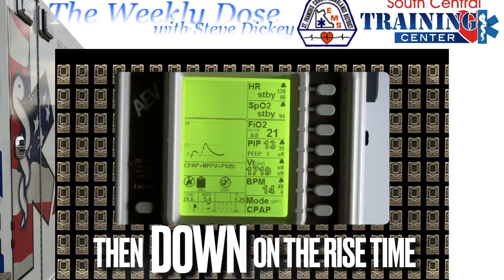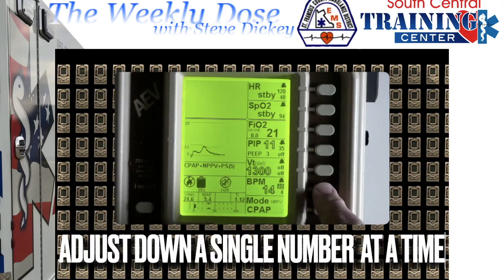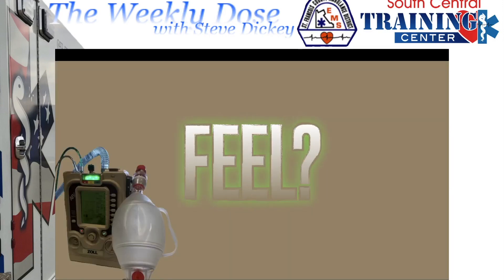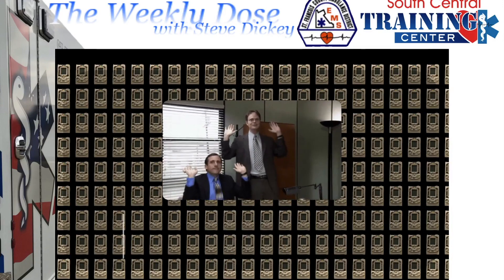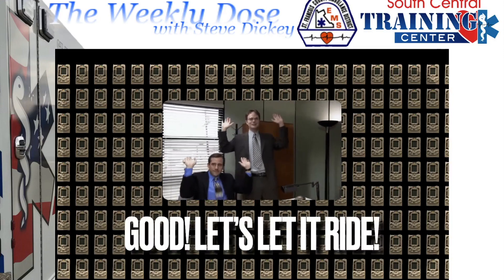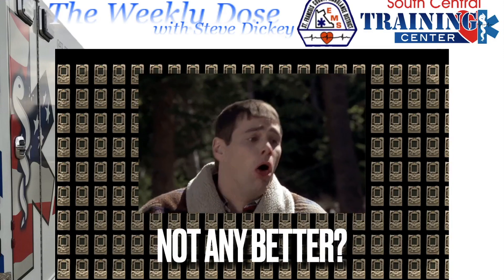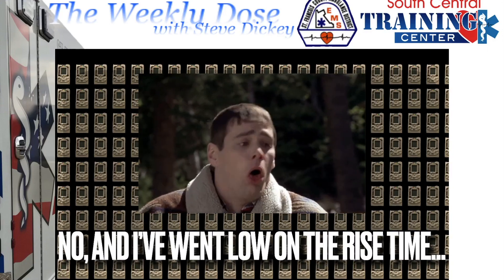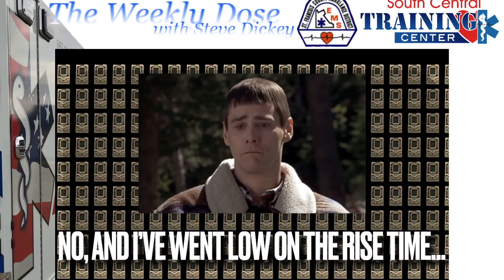When they're suffocating and cannot pull enough air in, go down first. Adjust down by a single number and work from there. Does that feel better? Good — let's let it ride. Not any better? If you've gone low on rise time and they're just not getting better, move on.